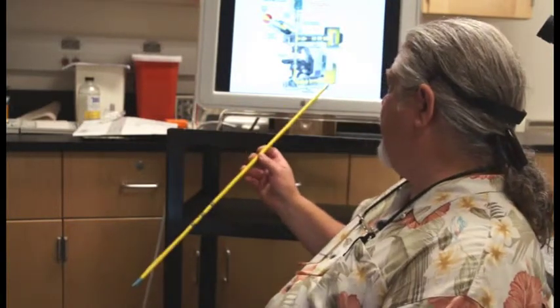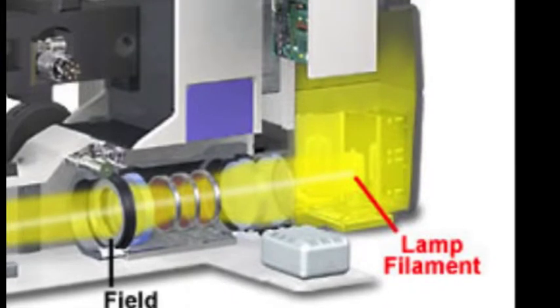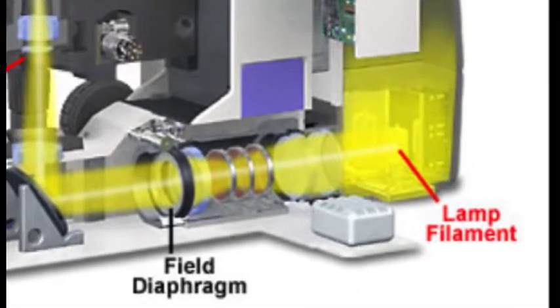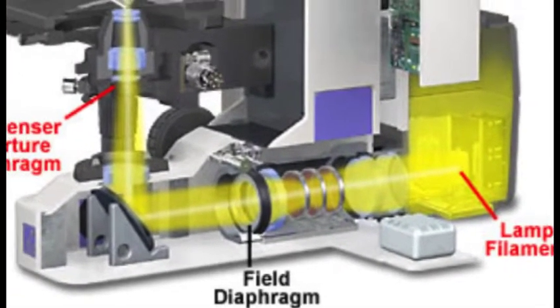Now let's discuss Köhler illumination, or alignment of the microscope. And to do that we're going to refer back to an earlier diagram that we used previously that shows you the field diaphragm in the microscope. Remember, the light leaves the illuminator and travels through the field diaphragm on its way up to the stage.